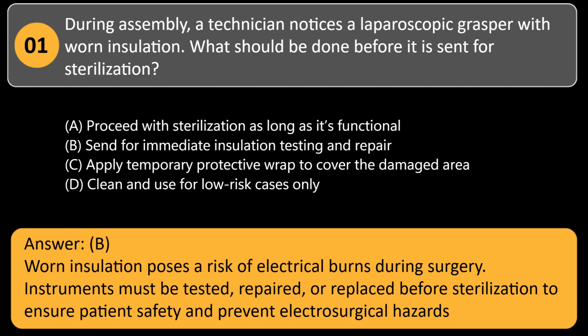During assembly, a technician notices a laparoscopic grasper with worn insulation. What should be done before it is sent for sterilization? A. Proceed with sterilization as long as it's functional. B. Send for immediate insulation testing and repair. C. Apply temporary protective wrap to cover the damaged area. D. Clean and use for low-risk cases only. Answer: B. Worn insulation poses a risk of electrical burns during surgery. Instruments must be tested, repaired, or replaced before sterilization to ensure patient safety and prevent electrosurgical hazards.